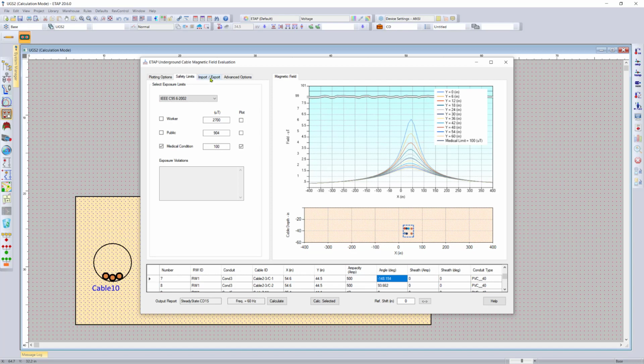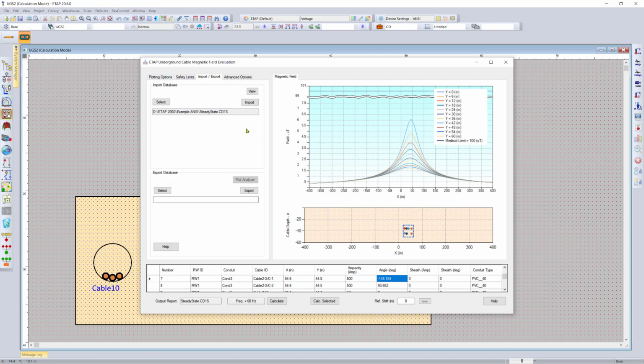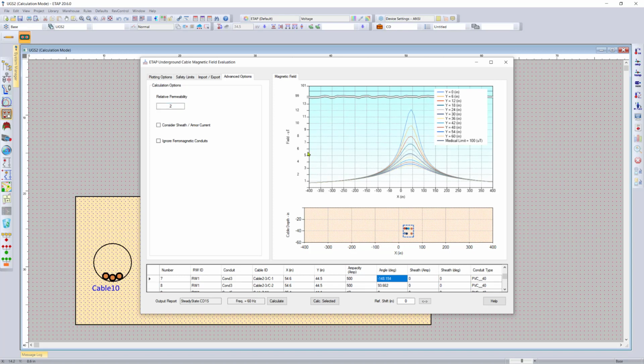You can also use the underground cable magnetic field calculator to manually select the underground raceway system results. You can also export the results to an external database or send it to the plot analyzer. And you can also consider sheath and armor current, ignore ferromagnetic conduits, or even change the relative permeability of air. The tool therefore allows you to evaluate 3 magnetic field exposure limits, which are worker, general public, and individuals with medical condition. The biggest value of this tool is to determine if personnel sensitive to the potentially harmful effects of the magnetic field exposure, such as individuals with pacemakers, are not being exposed to long-term magnetic fields above the recommended limits.